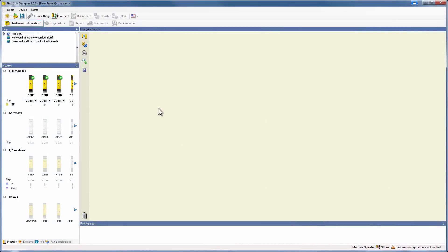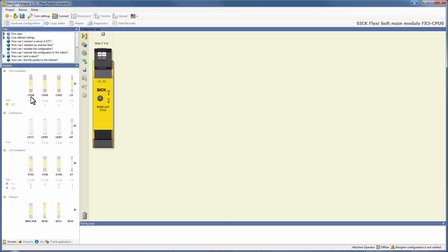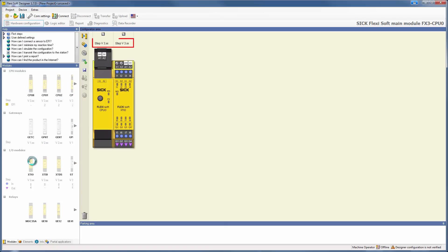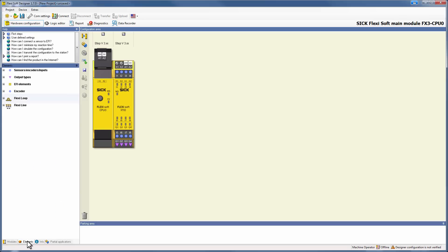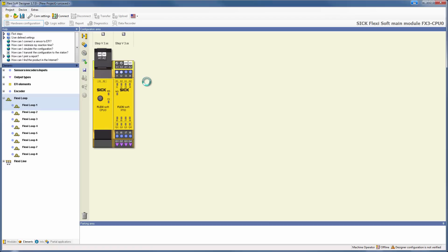Let's start by configuring the hardware. In this example we will use a CPU 0 and an XTIO. Both of them need to be at least version 3. After that we can switch to the elements, then to the category FlexiLoop and add FlexiLoop 1 via drag and drop. That's it. We added FlexiLoop to our FlexiSoft station.